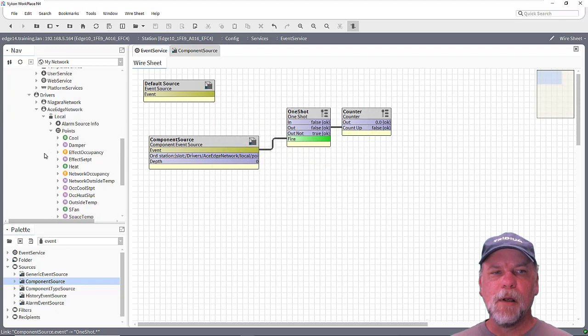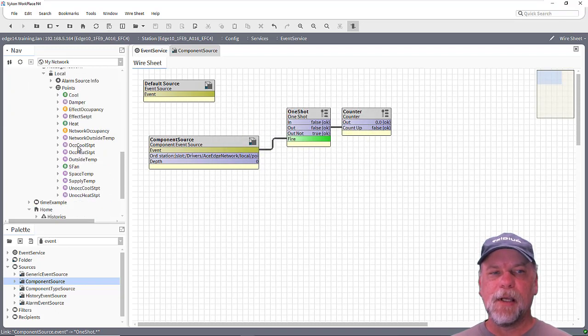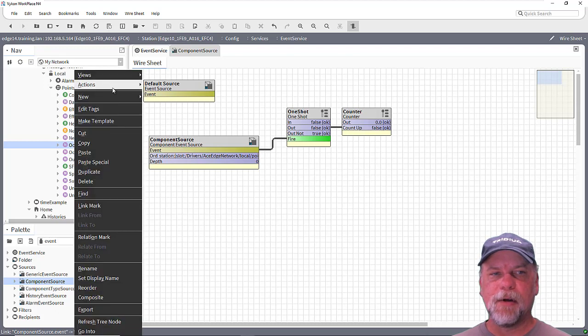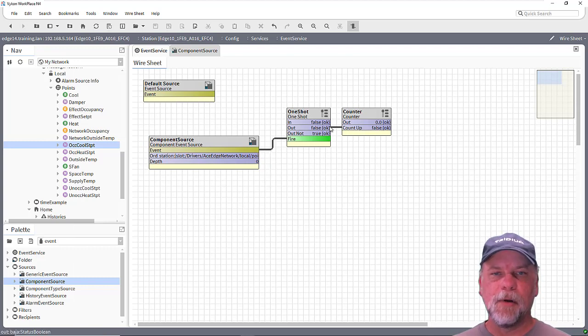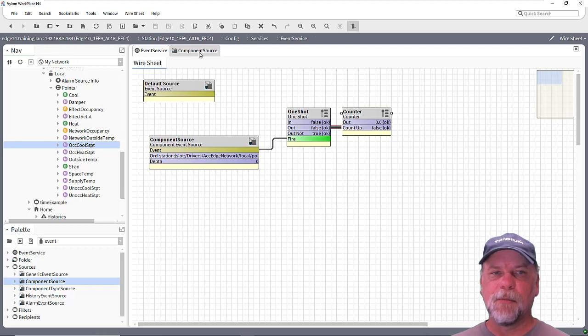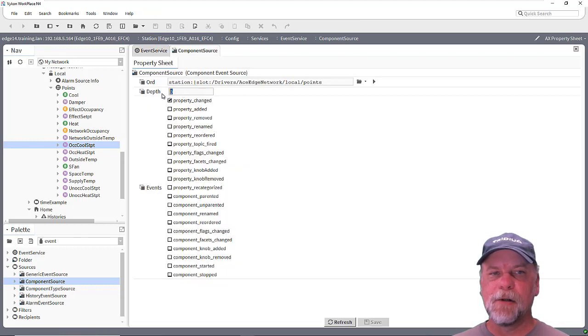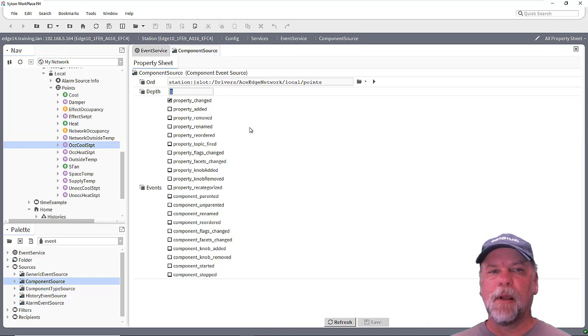So under the points container, if I were to change something — like if I went in here and invoked a set action on the occupied cooling set point — you'll notice that the counter does not increment. The reason being is the component source is set with a depth of zero, which means just monitor that component and its direct properties.